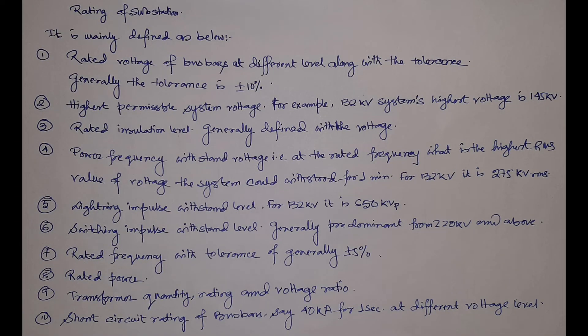Now we will check how the rating of a substation is defined. The first criteria is the rated voltage of the bus bar at different levels. A substation can consist of different voltage levels, so you have to define the voltage levels of the bus bars along with the tolerance — generally plus or minus 10%. For example, for a 132 kV / 33 kV substation, the defined voltage at the 132 kV level will be 132 kV ±10%, and at the 33 kV level it will be 33 kV ±10%.